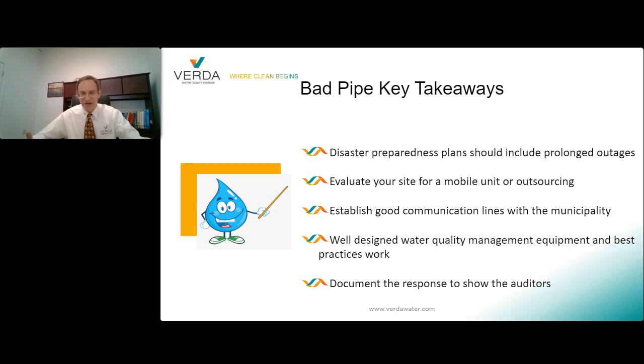Three, your system may be operational, it may be adequate, and it may be successful, but is it capable when it's stressed? So how close are you to that edge that you're operating your water system? Is the hospital's water treatment equipment designed to handle the unexpected? And if not, what happens when the unexpected happens? The hospital steam feed water did not meet AAMI TR 34 recommendations. And I'm guessing that the people in the SPS and the facility maintenance department didn't realize that. I mean, it was never a problem before for decades. And there was no incentive to change what they were doing until it became a problem, right? The old adage: it's not a problem until it is a problem, and then it's a big problem.